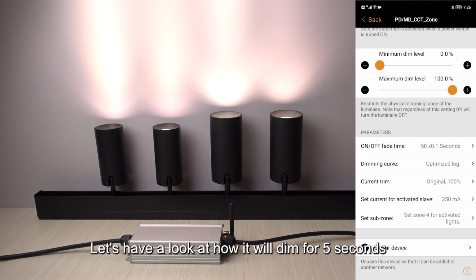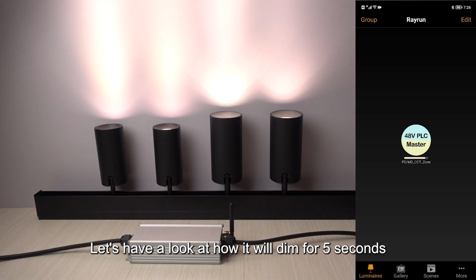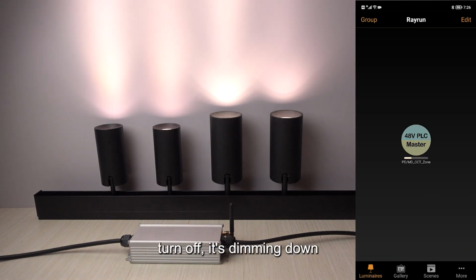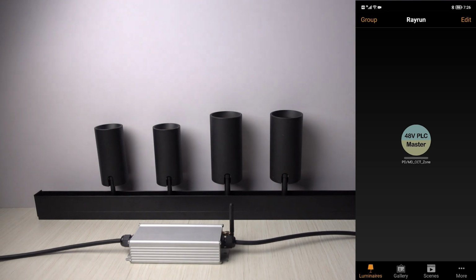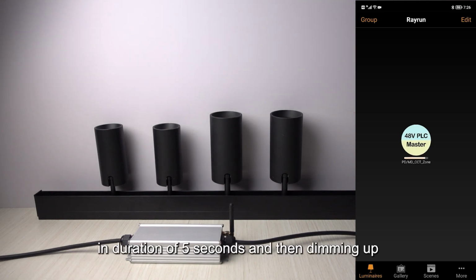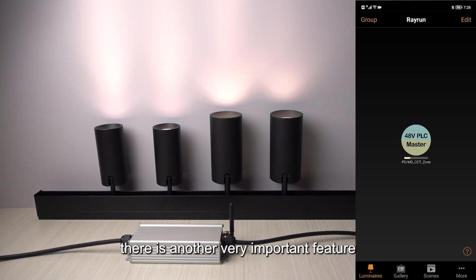Let's have a look at how it will dim for 5 seconds. Turn off, dimming down, in duration of 5 seconds, and dimming up. There is another very important feature for the slave drivers: we are using the full-time DC dimming to dim the light. It's not high frequency, so it is 100% flicker free.